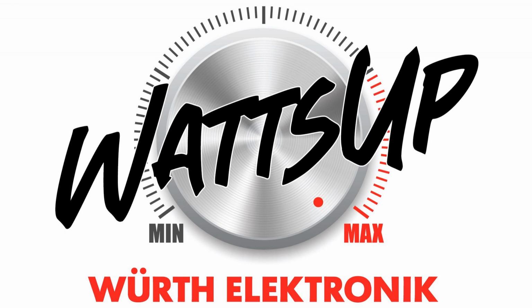For instance, the frequency band is already here, so I can just select it and still modify the start and stop frequency. According to CISPR, I don't even have to know that the resolution bandwidth is 9 kHz. The software does it for me, and I can set the dwell time and sweep mode. In amplitude, you can take into consideration external losses and the internal LISN. Since I'm using the internal LISN, I'm already compensating for it.